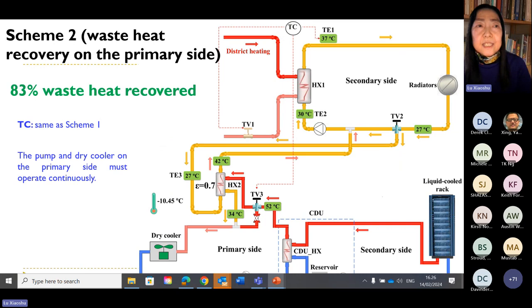And this is our invention scheme two that recovers waste heat from the primary side. About 83% of waste heat can be recovered. The design is quite similar to the first one, except that in the middle, you can see that the heat exchanger recovers waste heat from the primary side instead of the secondary side. So that's the only difference. The control process is the same as scheme one, but there is a very, very big difference.